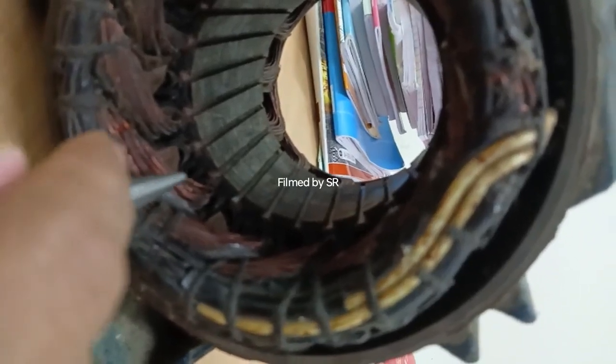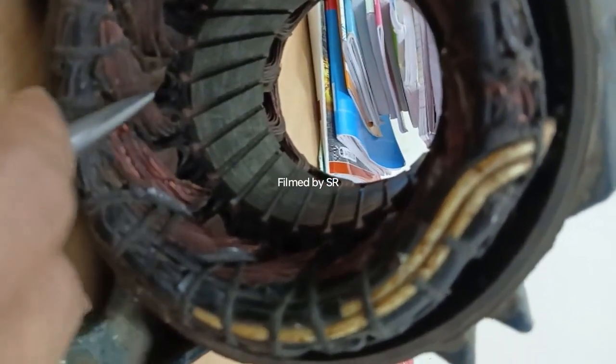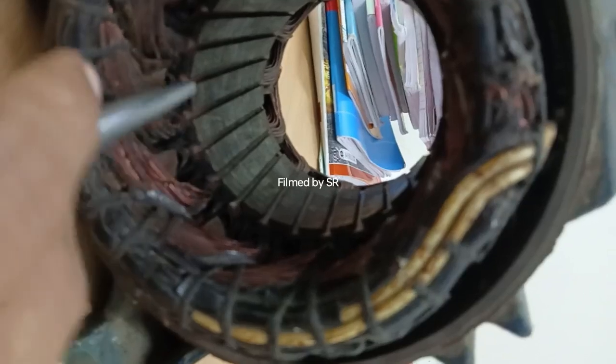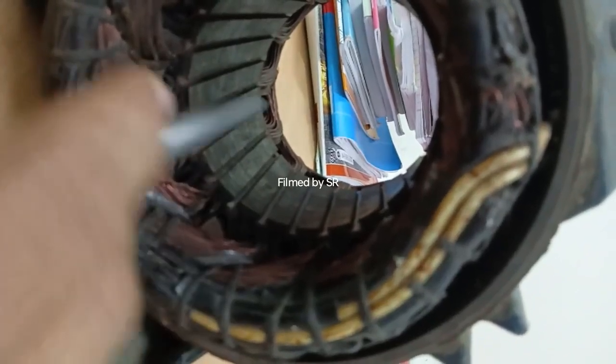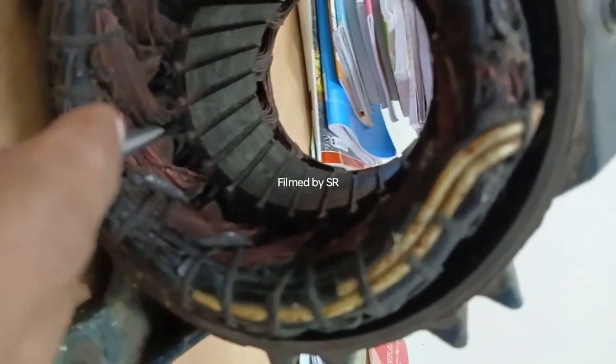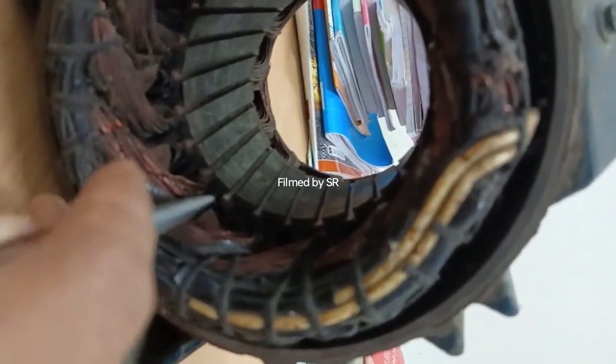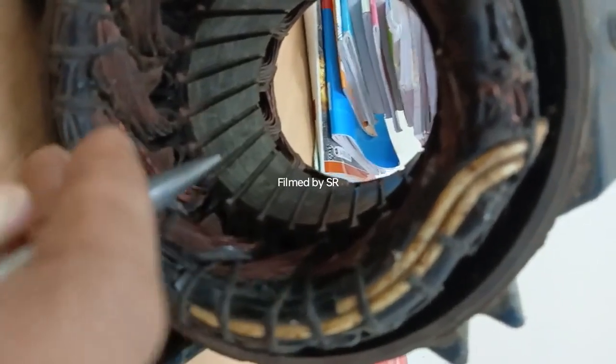Because if you place coils entirely in the bottom layer, then that coil will mostly find its flux path cheaply through iron. And if you place a coil entirely in the top layer, it will find its flux path through iron and air, and therefore the magnetic circuit will become uneven, and that will create an unbalance in the end.